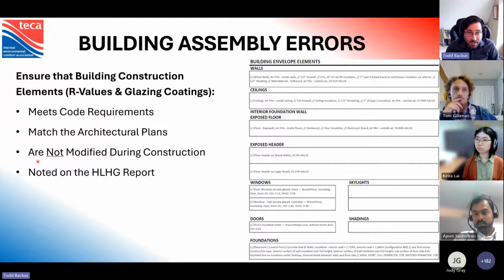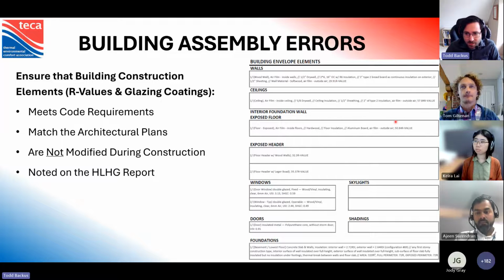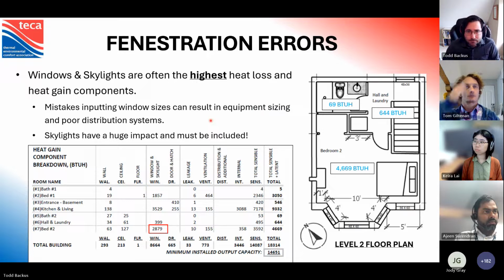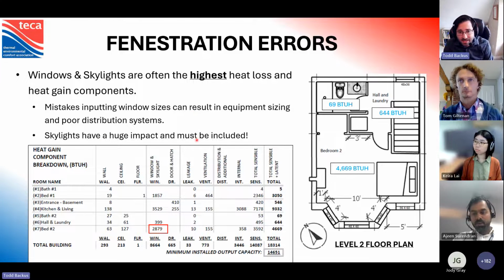I've seen the RSI values used instead of R values, or USI. So just be very careful that the units are correct, and they should be printed in these write-ups here as well. So it should be noted on the heat loss heat gain report directly. Fenestration errors. Because the windows and skylights are the highest loads, you really want to check those and make sure that the assembly's correct and that you haven't missed any of them, because missing a skylight is going to have a noticeable impact. That's going to be a pretty major error.